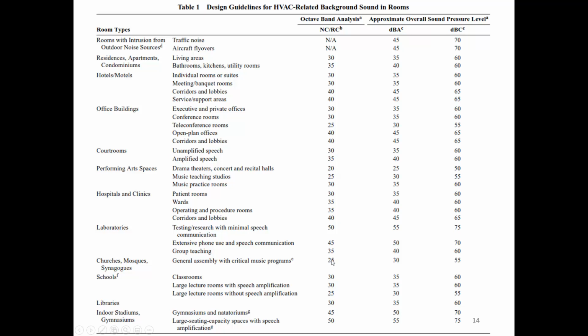So general assembly with critical musical programs, this might be like a high school auditorium or a church, would be 25. Classrooms are 30. In a residence, a private living area would be 30, but if it's more like the bathroom or the kitchen, 35 would be okay. Offices, if it's a private executive office or teleconference room, you might be at that 25 to 30. And if you went up to a basic private office, you can be 35. I guess they still put that in 30, but usually 35 could be okay for that if it's not executive.